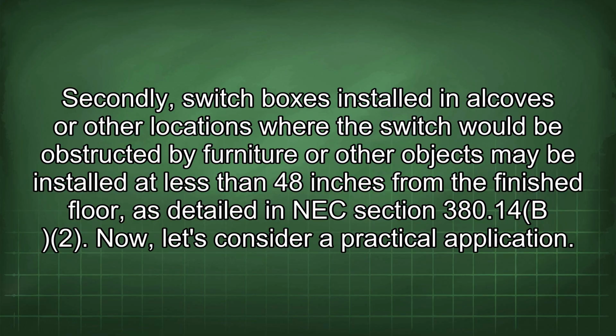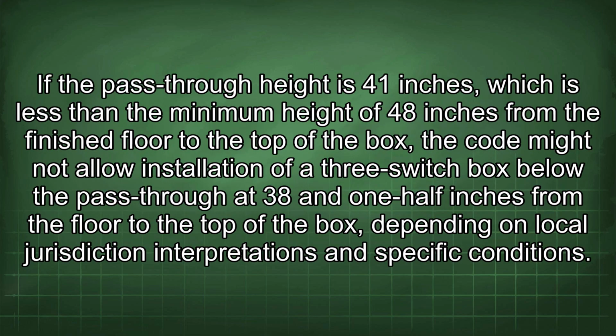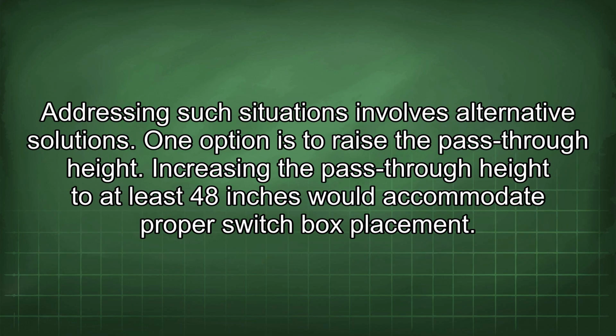Now let's consider a practical application. If the pass-through height is 41 inches, which is less than the minimum height of 48 inches from the finished floor to the top of the box, the code might not allow installation of a 3-switch box below the pass-through at 38.5 inches from the floor to the top of the box, depending on local jurisdiction interpretations and specific conditions. Addressing such situations involves alternative solutions.